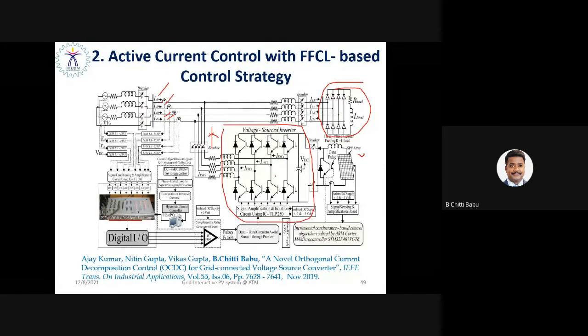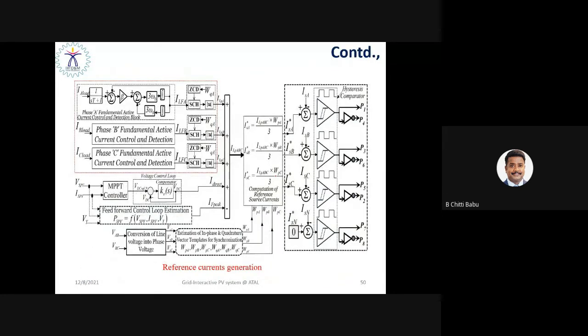And here, the control algorithm that we used is active current harmonic control with the help of a sample and hold circuit and a zero order hold circuit, and a zero crossing detector. Here it doesn't need any phase locked loop for estimating the value of theta. Instead, we used a zero crossing detector as the unit vector template, so that the control complexity is largely reduced with the help of this proposed control strategy.